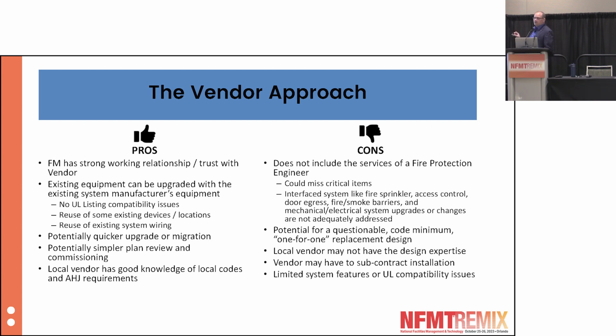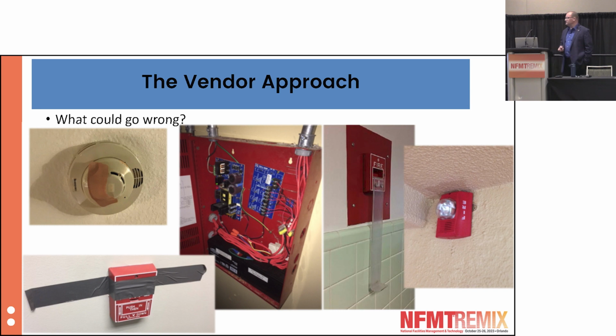A true Band-Aid approach. This is a real picture. A friend of mine took this picture not more than 1 year ago. This is a sounder-based smoke detector installed in a hotel room. The HVAC diffuser is about 20 inches away from that smoke detector. The air blows constantly on it and was putting the device into alarm. So instead of moving the device or moving the diffuser or changing the diffuser's air pattern, they simply put a Band-Aid on the smoke detector to make that happen.